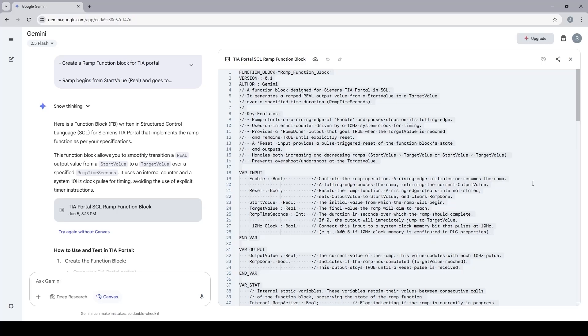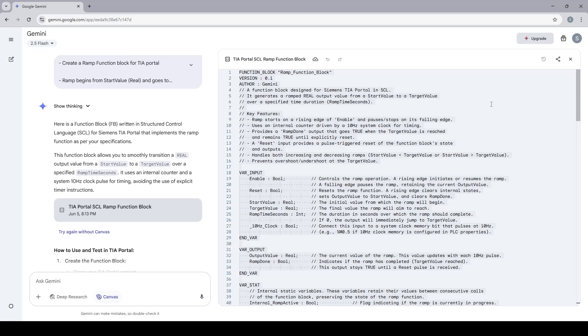It's a lot of admin work, right? That saves you tons of time. This code has been generated in SCL language. SCL stands for Structured Text Language and is one of the five standard PLC programming languages specified in the IEC 61131-3 standard. SCL language is very similar to Pascal and is really easy to follow and understand. The next step is to save this code as an SCL file and then insert it in TIA Portal.